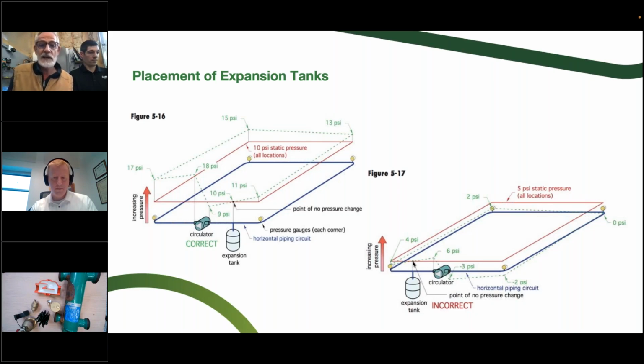So that 10 PSI fill pressure, in this case on the right, we use the 5 PSI fill pressure. You can see what happens as we go around there. We're going down in pressure, down in pressure. We get to the third bend there. We're down to 0 PSI. As we come down to the end there, now we've got a negative. Now we've got a subatmospheric condition in our system.